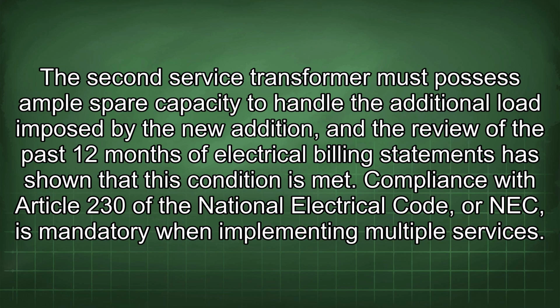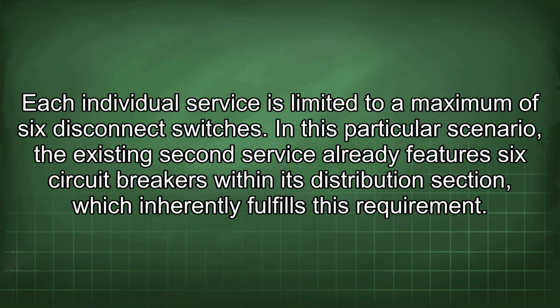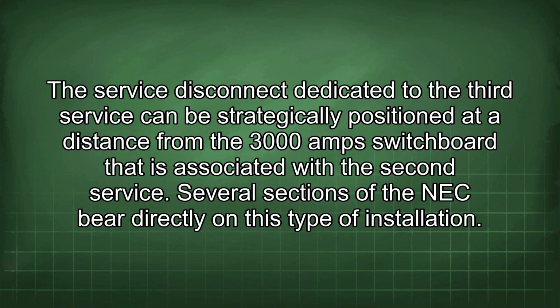Compliance with Article 230 of the National Electrical Code, or NEC, is mandatory when implementing multiple services. Each individual service is limited to a maximum of 6 disconnect switches. In this particular scenario, the existing second service already features 6 circuit breakers within its distribution section, which inherently fulfills this requirement. The service disconnect dedicated to the third service can be strategically positioned at a distance from the 3000 amp switchboard that is associated with the second service.